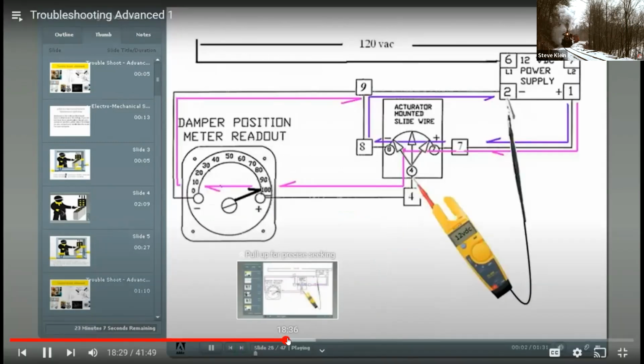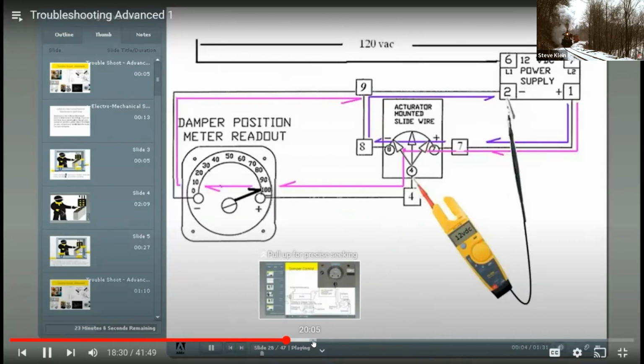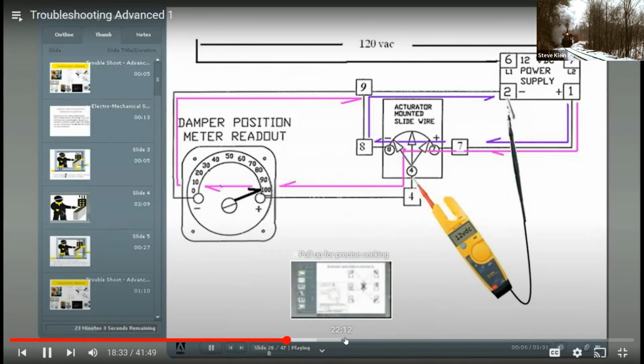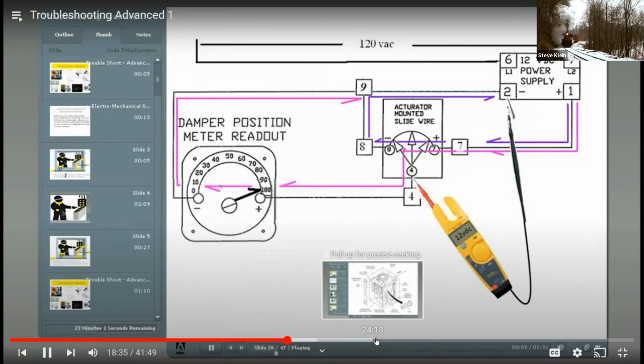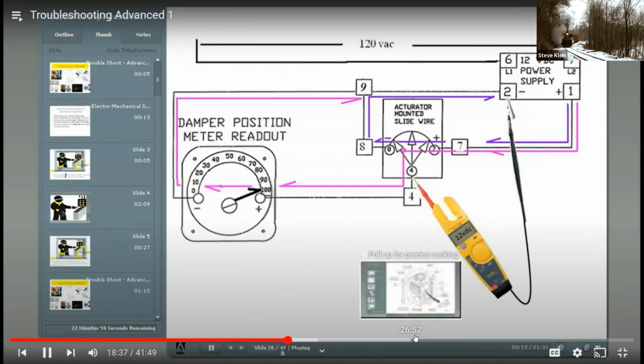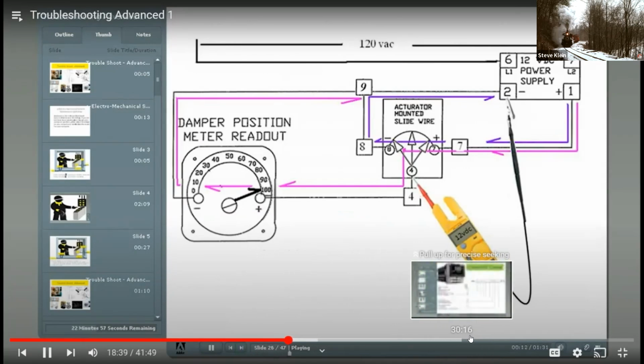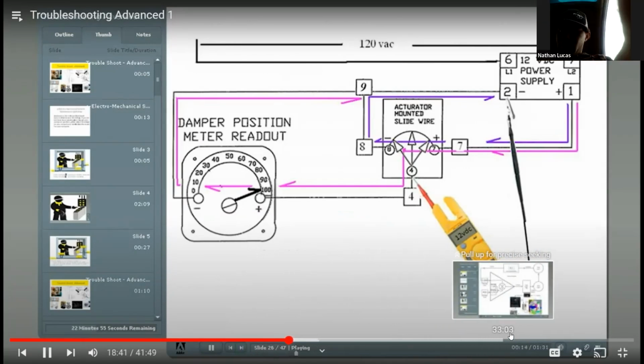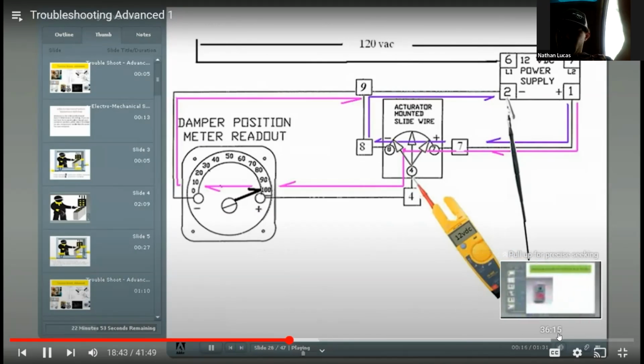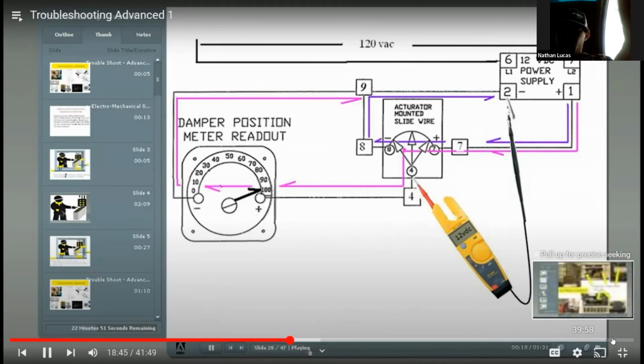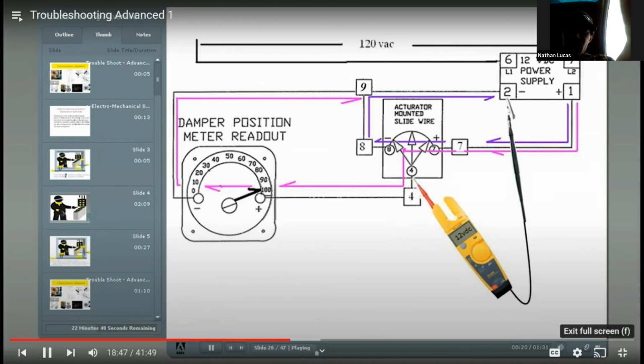The correct answer is C. The wire between terminal 8 and terminal 9 is broken. No matter where the wiper is positioned on the slide wire, panel meter and the test meter both read 12 volts DC. The only causes for that would be the wire between terminal 8 and 9 is broken, or the wire between terminal 8 and the pot 8 is broken.